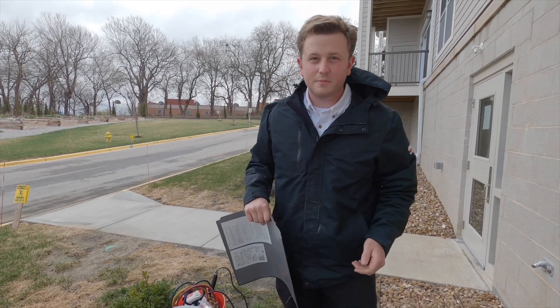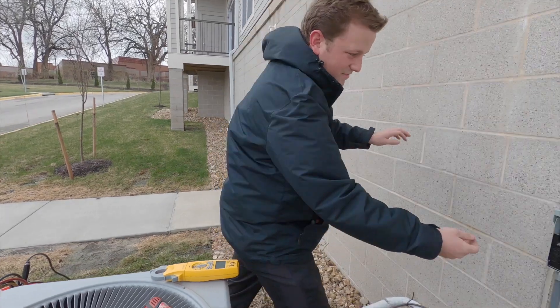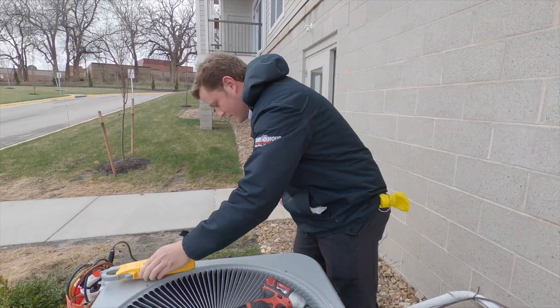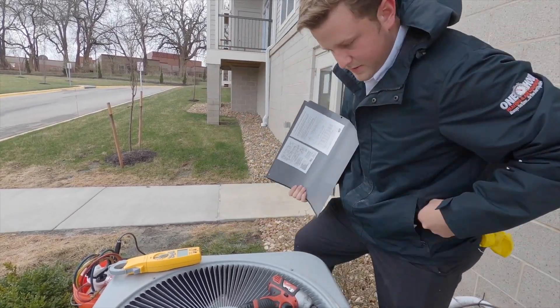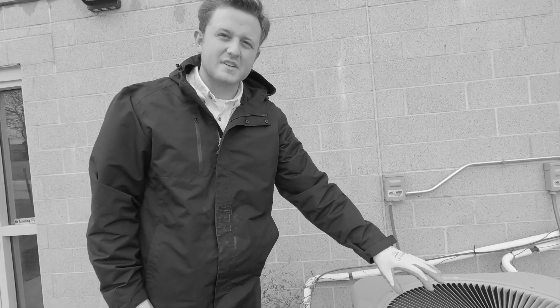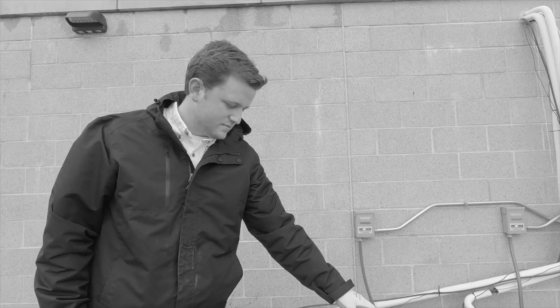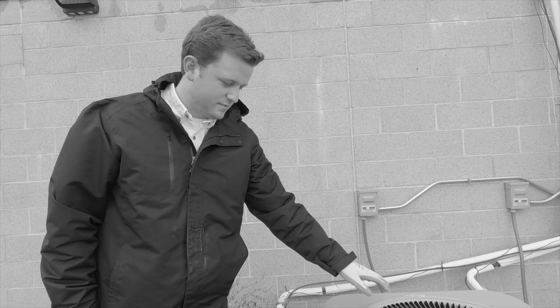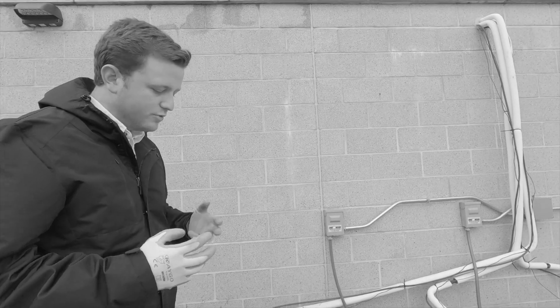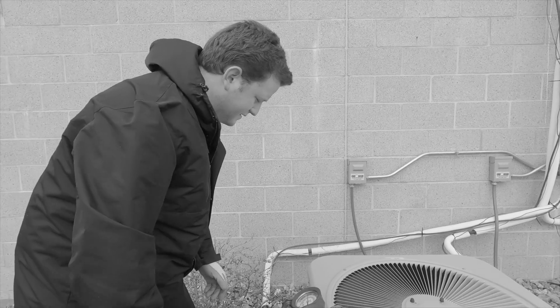1.7 amps is the maximum amperage, so we're well under that. I like to shut it off when I'm putting the door back on, because one little slip and you could shock yourself. We should see something a little higher than 40. The compressor is making kind of a chatter or ticking noise — we'll want to come back on a warmer day and check it when there's an actual load, humidity to remove, things like that. We'll just notate that and come back.